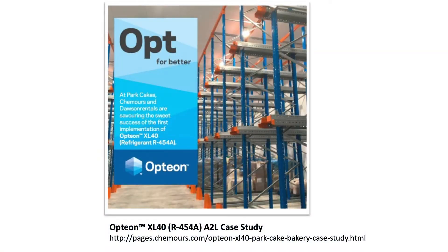Even some distributed systems — I'll throw a link below to a case study we were involved with over in Europe, actually putting an A2L in a cold storage system. Those can be done. You have to do the risk analysis, understand the occupancy of the space, the size of the charge — a lot of steps to ensure it's done safely, but those can and have been done. We expect those types of applications to continue to grow in the future.